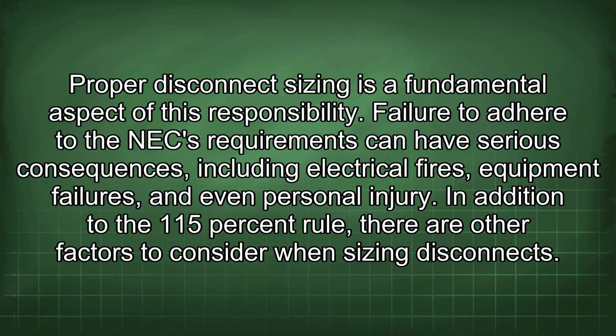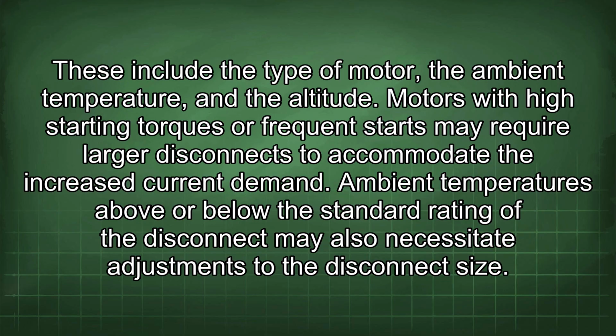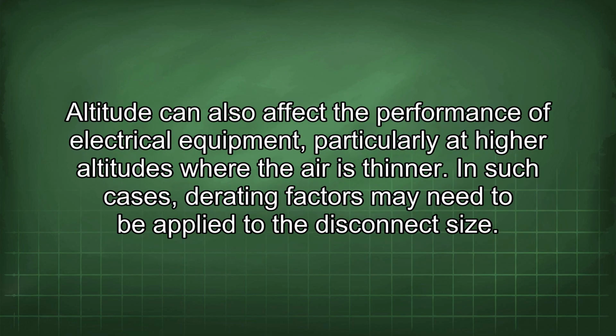In addition to the 115% rule, there are other factors to consider when sizing disconnects. These include the type of motor, the ambient temperature, and the altitude. Motors with high starting torques or frequent starts may require larger disconnects to accommodate the increased current demand. Ambient temperatures above or below the standard rating of the disconnect may also necessitate adjustments to the disconnect size. Altitude can also affect the performance of electrical equipment, particularly at higher altitudes where the air is thinner. In such cases, derating factors may need to be applied to the disconnect size.